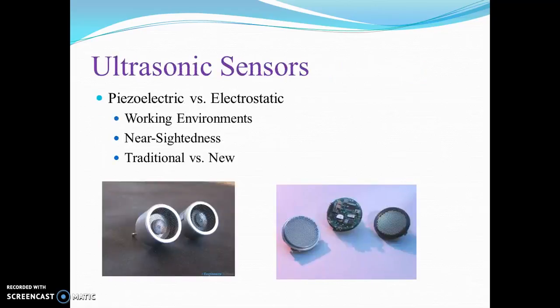Here are the ultrasonic sensor types, which are piezoelectric and electrostatic. Piezoelectric can be used in rugged environments because the ceramic can be sealed in housing, whereas the electrostatic blocking distance is just 4 or 6 inches, while piezoelectric is 12 or 18 inches. Piezoelectric has been around for many years, when crystal was first being used for transducers. Electrostatic was first used when the silicon machining process began.